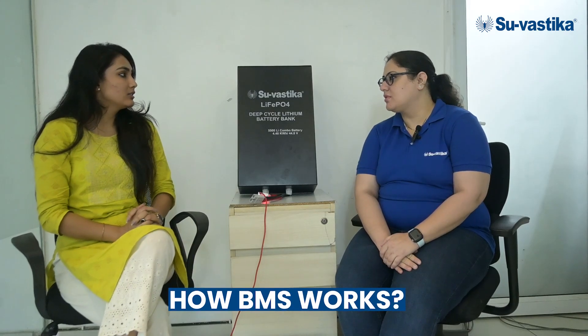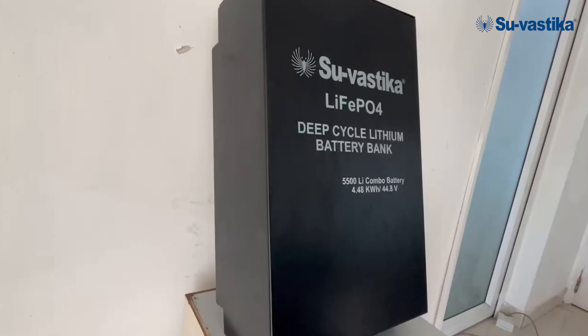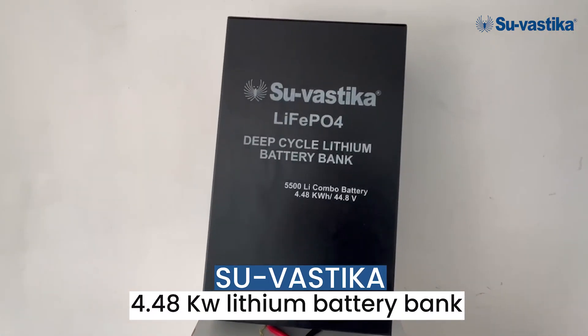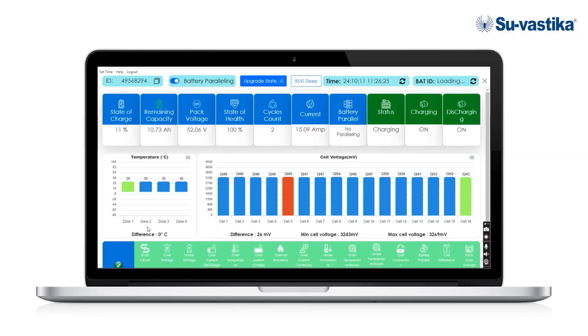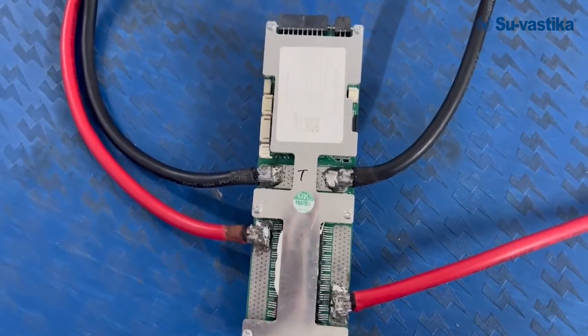How does BMS work? Every lithium battery is made of different cells. For example, this Su-vastika lithium battery, which is a 4.48 kWh lithium battery bank, is made of 14 cells. Each cell has its own voltage, and we need to maintain the cell voltages of each cell. So BMS regularly monitors and balances the cell voltages so that each cell works within the defined parameters.